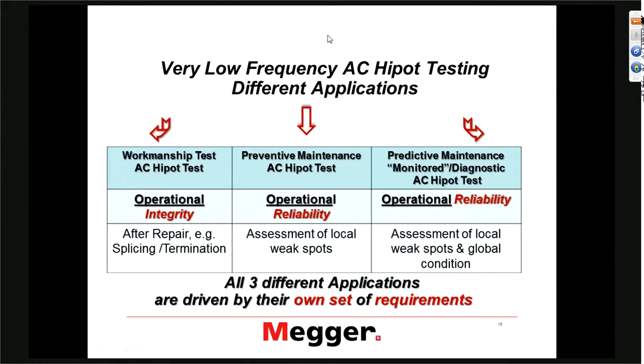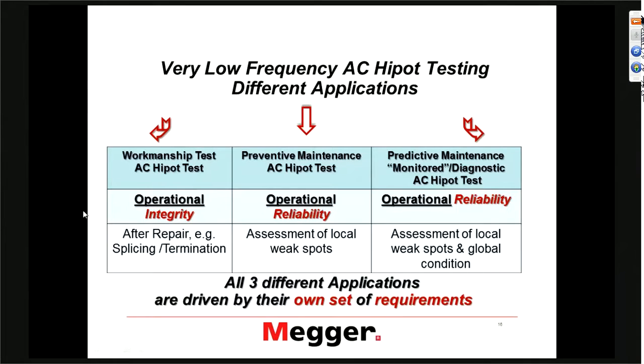When we look at very low frequency AC hipot testing, we have to recognize there are really three different applications, and when people talk about it we have to be clear what is meant. To the left, we have what we call the workmanship test — it tells you something about your operational integrity. That means I put a splice in, I test the cable, and I can be sure I can switch the cable in without the circuit basically blowing up.